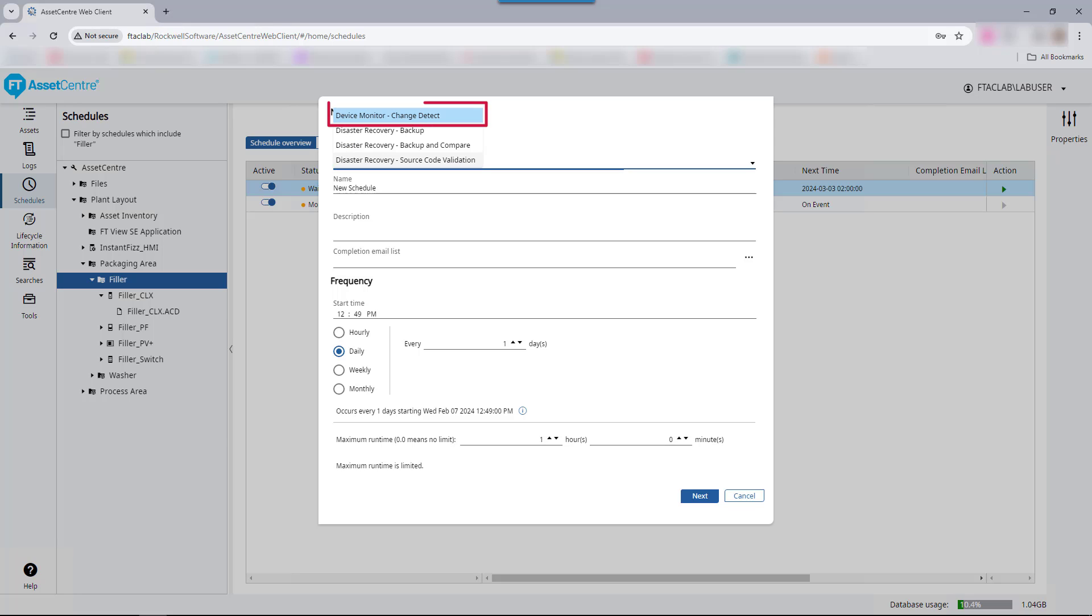A Change Detect schedule continuously monitors a version 20 or higher Control Logix asset for changes. Change Detect is a partnership between Factory Talk Asset Center and a configuration stored in the ACD file the controller is executing. The ACD file configuration determines what is considered a change. During execution, Factory Talk Asset Center polls each controller to determine if the change occurred. While not as detailed as Disaster Recovery Compare Report, this feature provides near real-time feedback on the controller's change status.